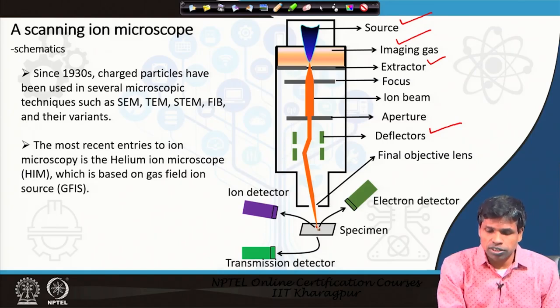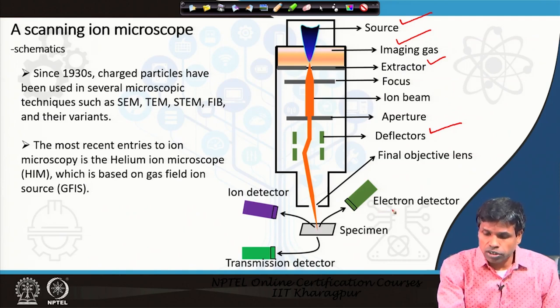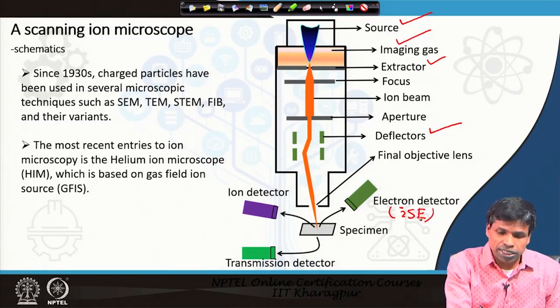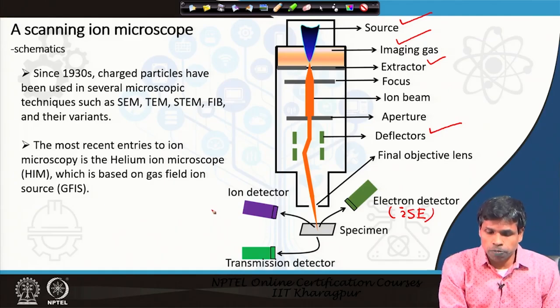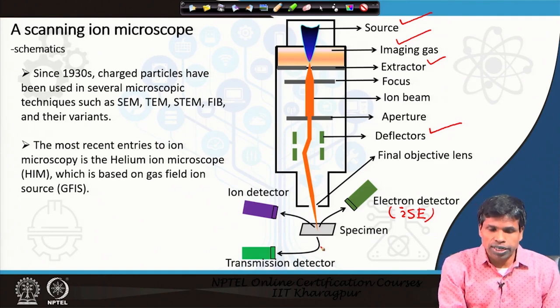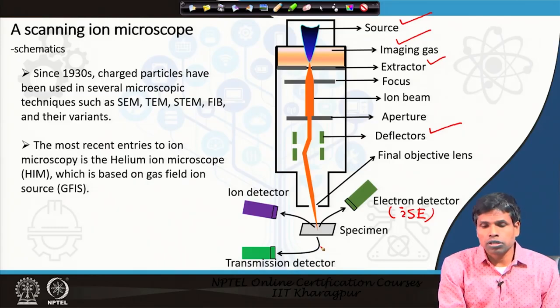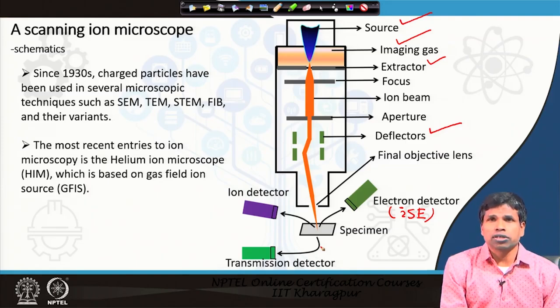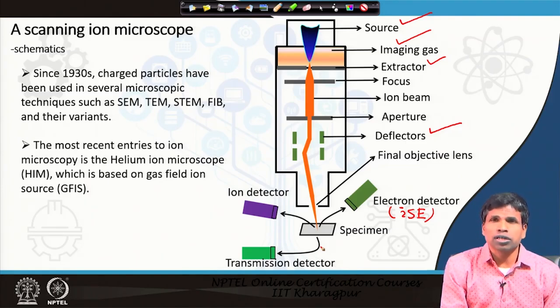Once the ion beam is incident on the specimen, we have an electron detector — that is the secondary electron detector — and we have a backscattered ion detector. We can also have a transmission detector, which we may discuss later. This is the typical schematic of the helium ion microscope. Ions have been used in microscopy for a long time for different purposes.